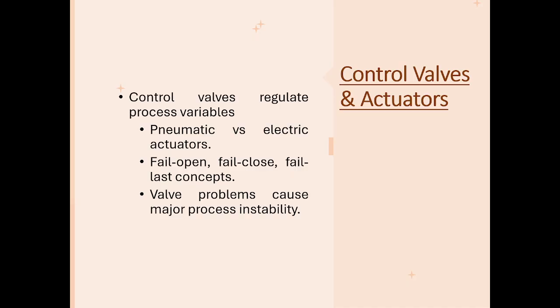So to move these valves, we use actuators. Some actuators use air pressure, so we call those pneumatic actuators, while others use electricity, and those are electric actuators. An important concept here is the fail action. When air or power is lost, should the valve fail open, fail closed, or stay in its last position? This decision is never about convenience. It's always about safety. All right, because many unstable processes that appear to be PLC or tuning problems are actually valve or actuator issues. So to understand how all these instruments and valves are connected, engineers rely on drawings, which takes us to the next slide.